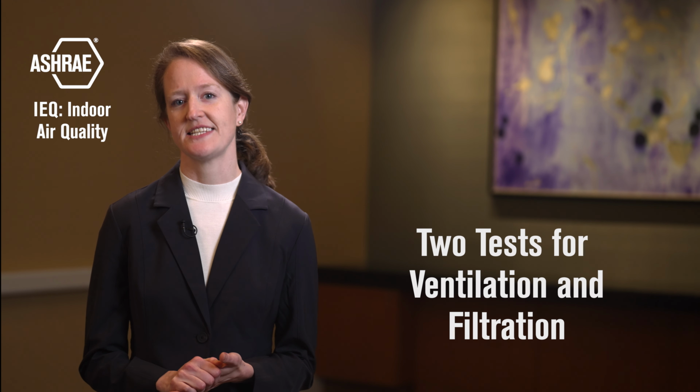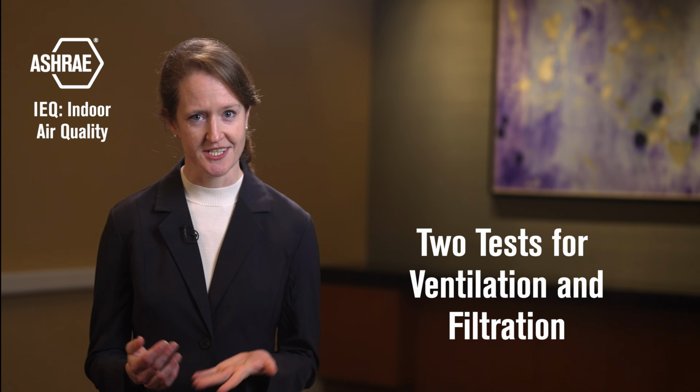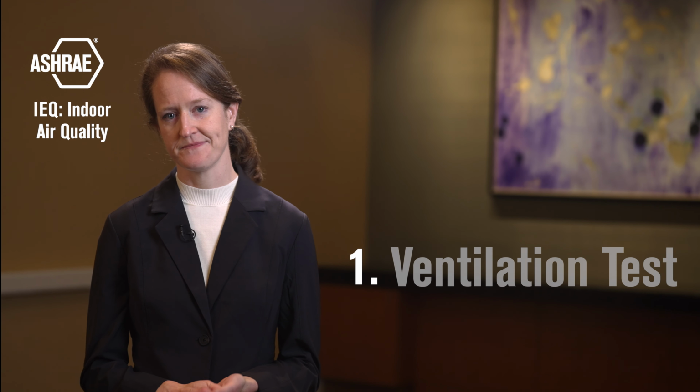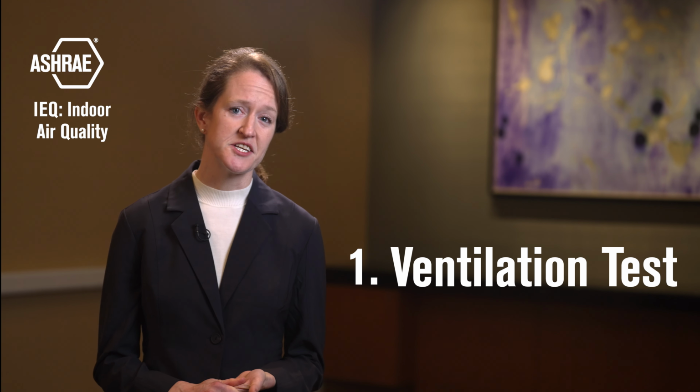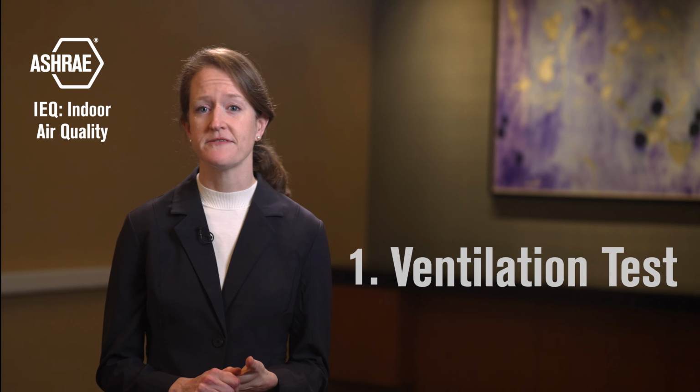With so many aspects of IAQ, where to start? I have two quick and easy tests for ventilation and filtration to find common conditions that degrade IAQ. They're not always found on maintenance checklists, but they can be done by any person with access to the air handling equipment. First, ventilation. Building codes and IAQ standards require some amount of outdoor air in every occupied space.